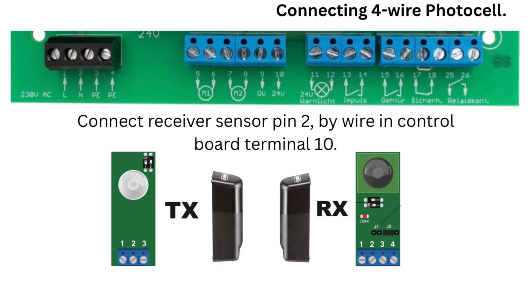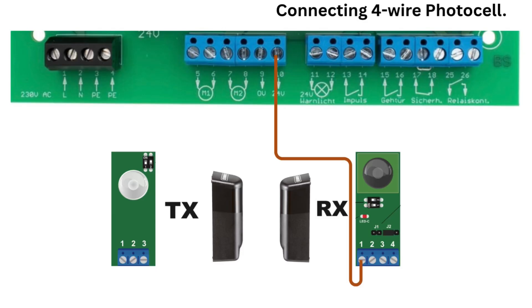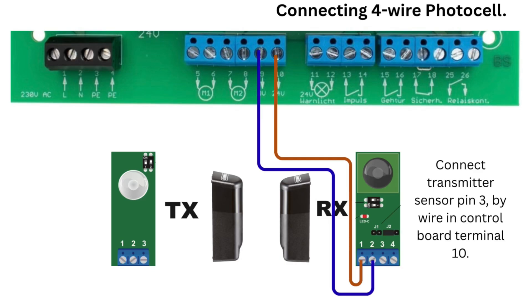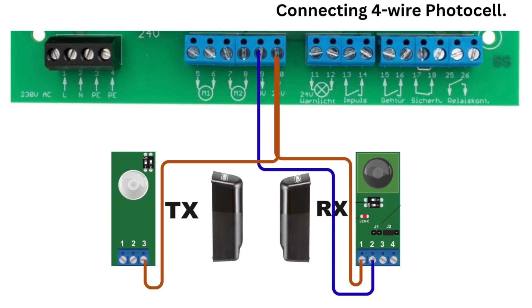Connect receiver sensor pin 2 by wire in control board terminal 10. Terminal 10 is plus 24 volt DC power supply output. Connect receiver sensor pin 1 by wire in control board terminal 9. Terminal 9 is negative 24 volt power supply output. Connect transmitter sensor pin 3 by wire in control board terminal 10. Connect transmitter sensor pin 1 by wire in control board terminal 9. Transmitter and receiver photocell power supply connection done.